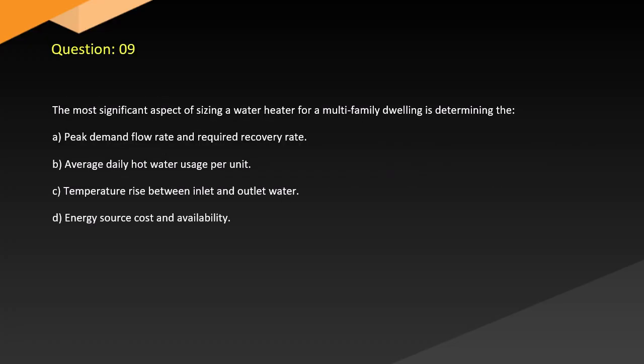Question 9. The most significant aspect of sizing a water heater for a multifamily dwelling is determining the A. Peak demand flow rate and required recovery rate. B. Average daily hot water usage per unit. C. Temperature rise between inlet and outlet water. D. Energy source cost and availability.